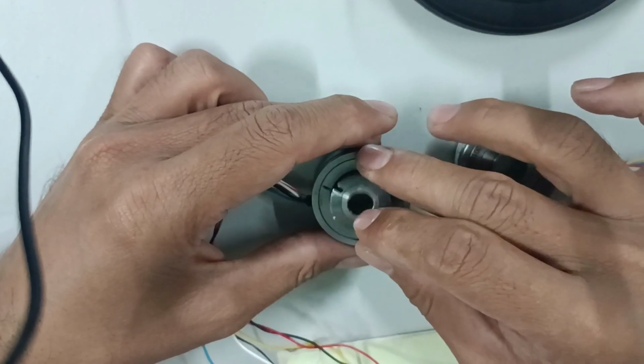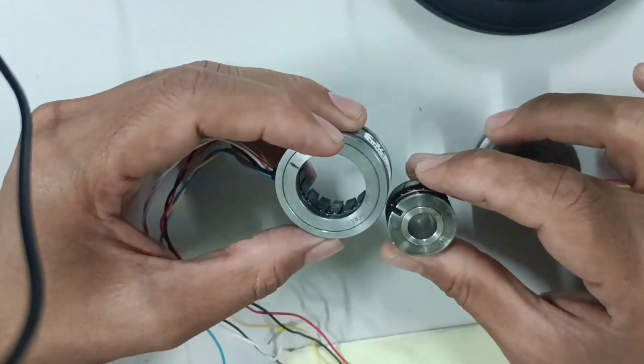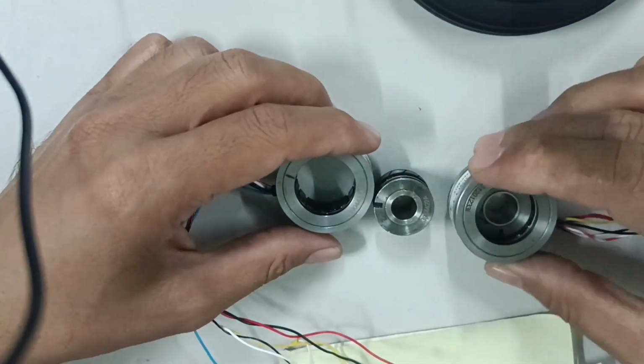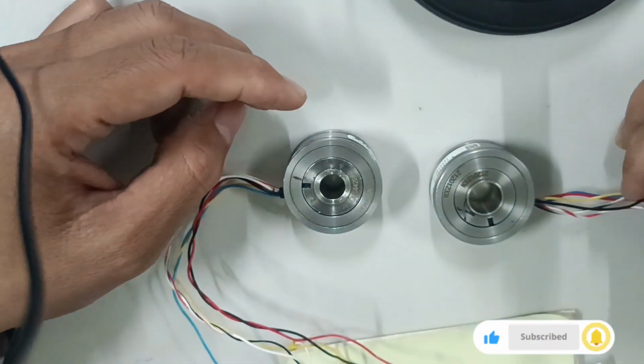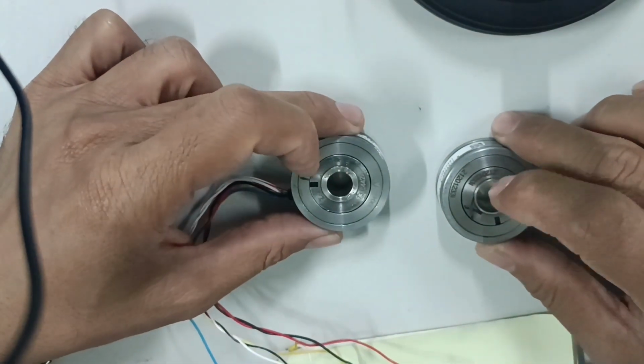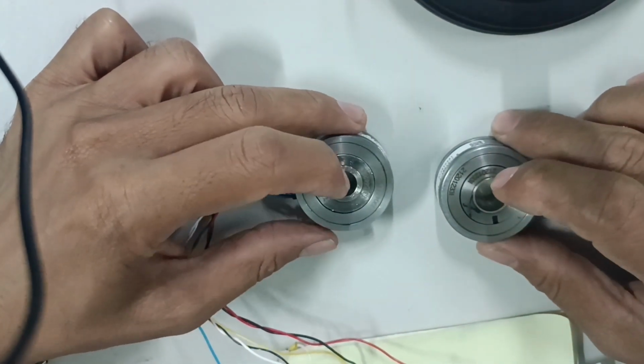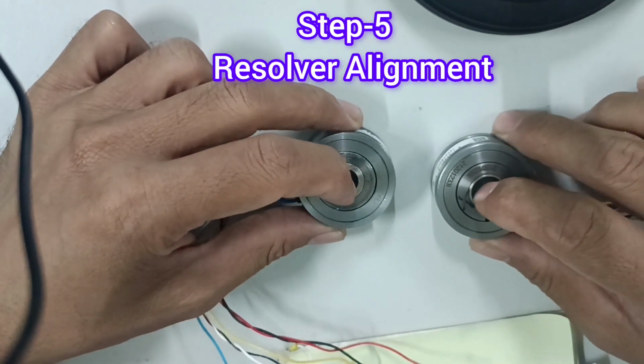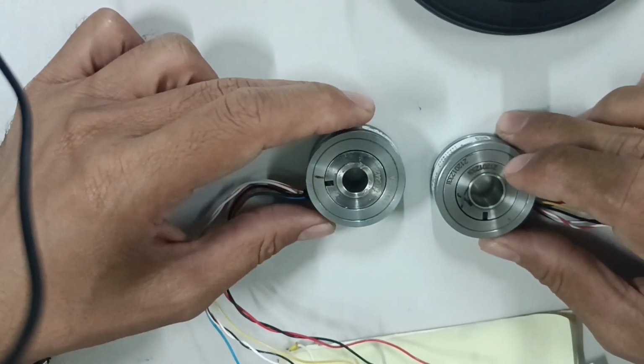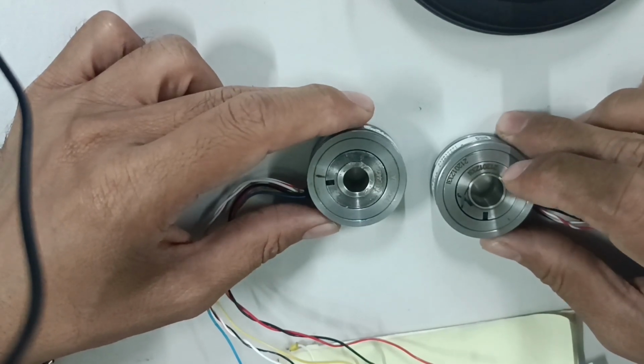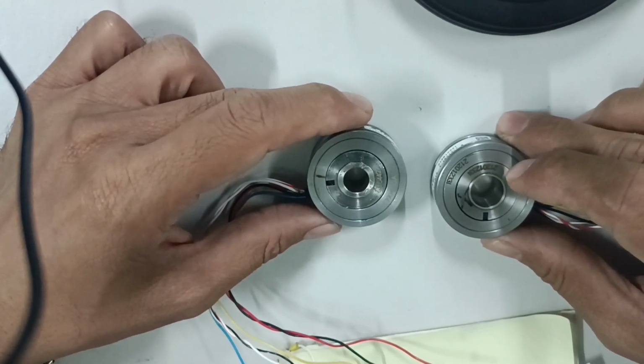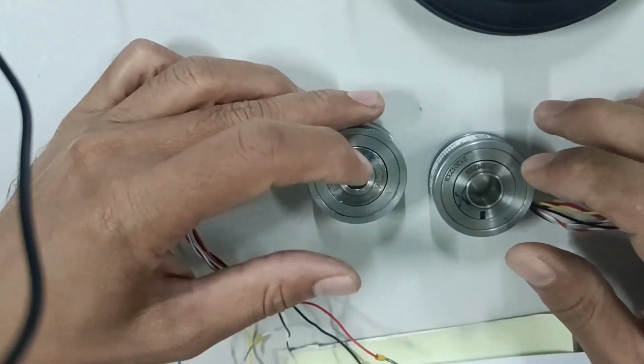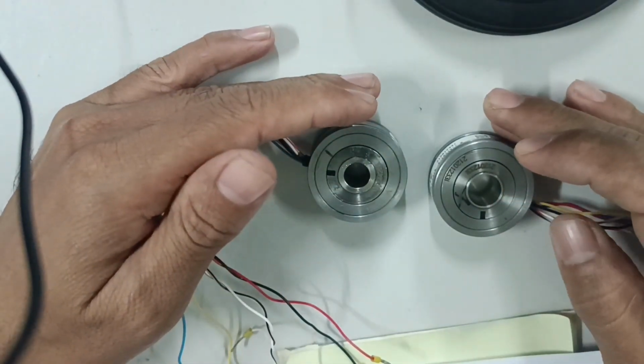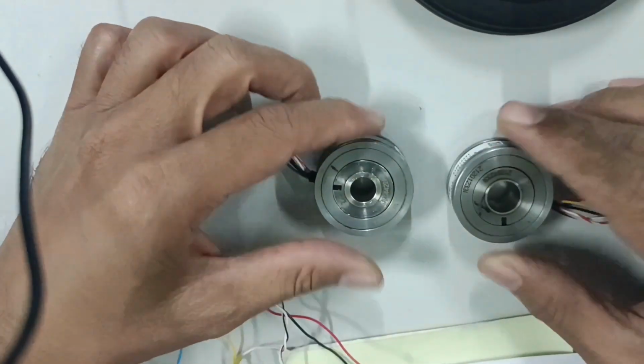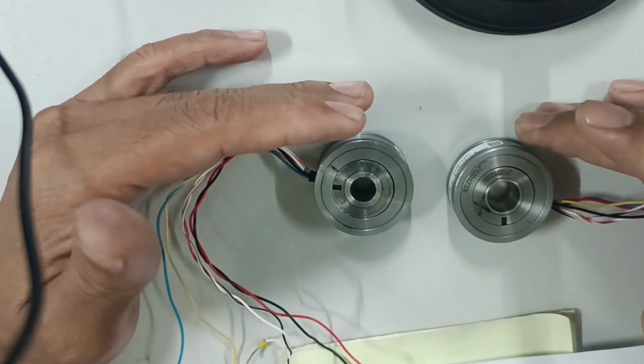Now step 4: verify the servo drive settings. Check that the servo drive is set to resolver mode, if applicable in your system or machine. Ensure the correct resolver excitation voltage and frequency in your settings. Reset the drive to factory default and reconfigure the resolver settings again in your system. Step 5: test resolver alignment. Incorrect resolver mounting can cause position error. Align the resolver mechanically according to the manufacturer specifications. Some systems allow software calibration to correct alignment issues.